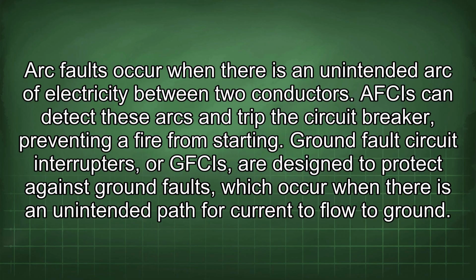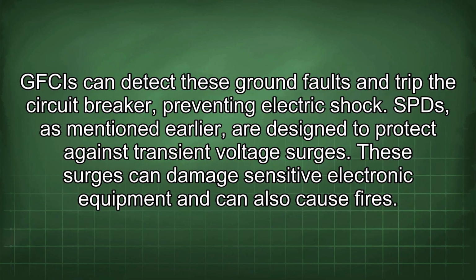Arc faults occur when there is an unintended arc of electricity between two conductors. AFCIs can detect these arcs and trip the circuit breaker, preventing a fire from starting. Ground fault circuit interrupters, or GFCIs, are designed to protect against ground faults, which occur when there is an unintended path for current to flow to ground. GFCIs can detect these ground faults and trip the circuit breaker, preventing electric shock.